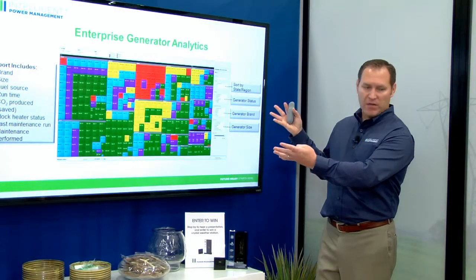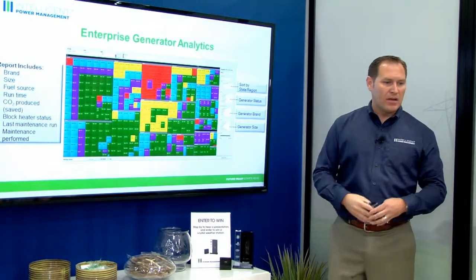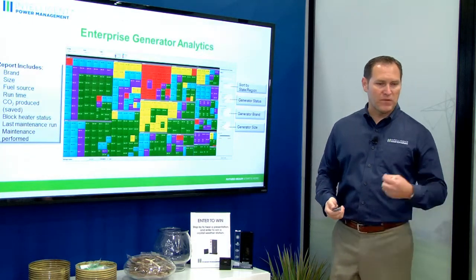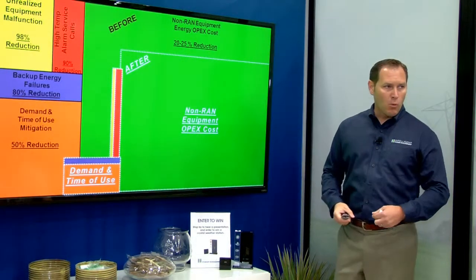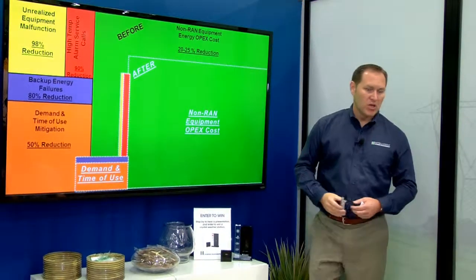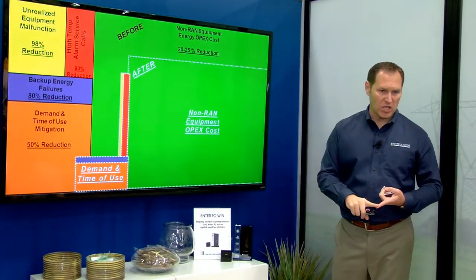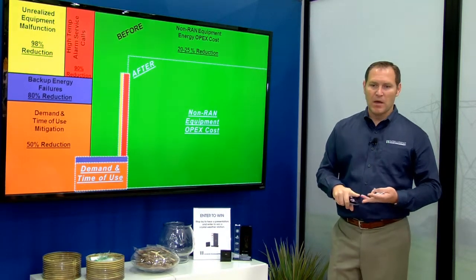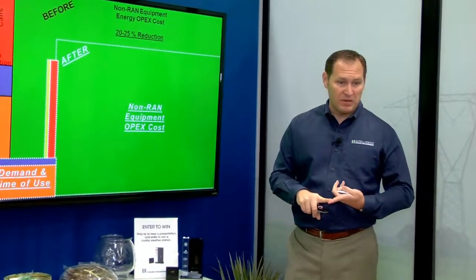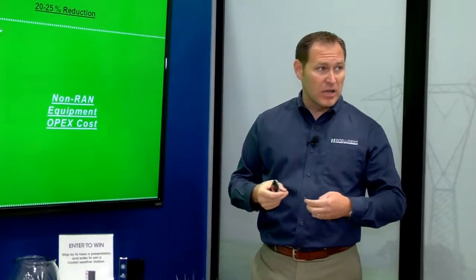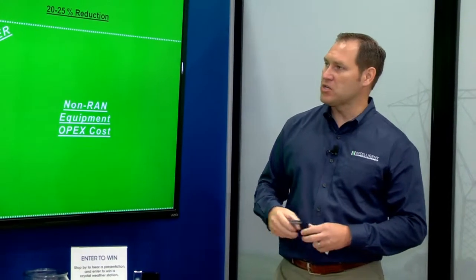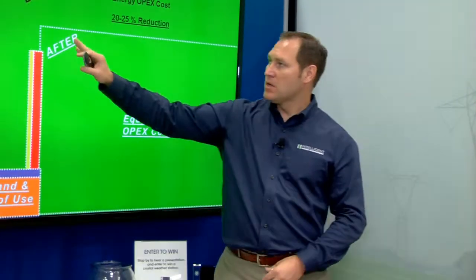This takes an enterprise view of data collected from each individual site, so we can let our customers know how efficiently or inefficiently their site is working. The key thing for us is to drive efficiencies. What we've learned so far: we've achieved a 98% reduction in unrealized equipment malfunction. We've found HVACs malfunctioning the customer didn't know about, dehydrators malfunctioning the customer didn't know about, public utility equipment on site pulling energy without the customer's knowledge, and legacy equipment 20 years old — all connections unplugged but the system still turned on consuming energy.